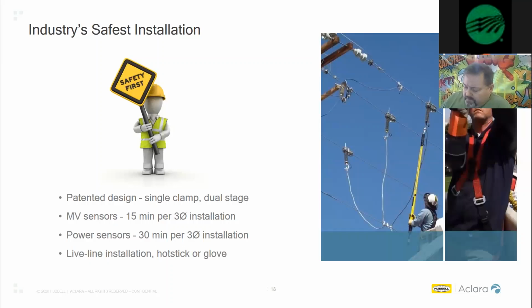So to be honest, the installation of just the MV sensors, like he's shown, at 15 minutes per set, is quite simple to achieve. You set the truck, you put the sensor on the end of a hot stick or glove, whatever your preference is, and you connect that to the hot stick clamp, and you connect to the sensor and just tighten down the clamp.